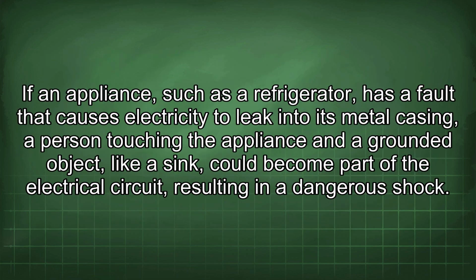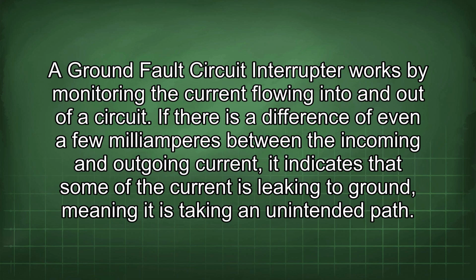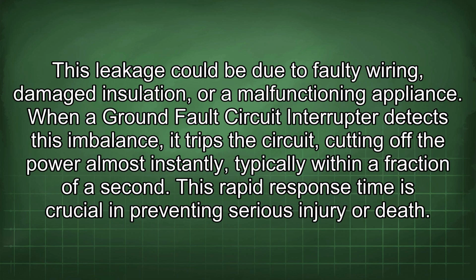If an appliance, such as a refrigerator, has a fault that causes electricity to leak into its metal casing, the person touching the appliance and a grounded object, like a sink, could become part of the electrical circuit, resulting in a dangerous shock. A ground fault circuit interrupter works by monitoring the current flowing into and out of a circuit. If there is a difference of even a few milliamperes between the incoming and outgoing current, it indicates that some of the current is leaking to ground, meaning it is taking an unintended path. This leakage could be due to faulty wiring, damaged insulation, or a malfunctioning appliance.